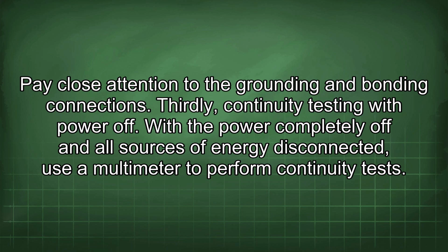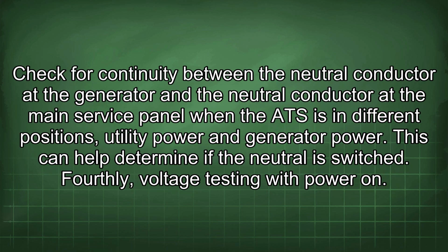Thirdly, continuity testing with power off. With the power completely off and all sources of energy disconnected, use a multimeter to perform continuity tests. Check for continuity between the neutral conductor at the generator and the neutral conductor at the main service panel when the ATS is in different positions, utility power and generator power. This can help determine if the neutral is switched.